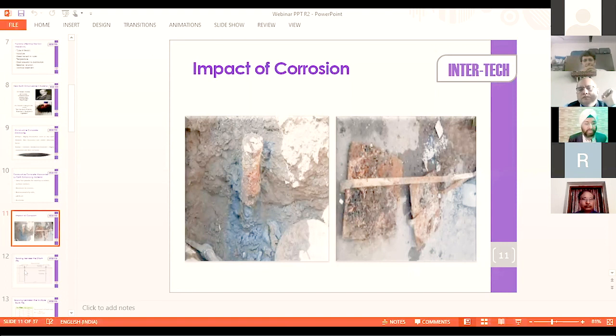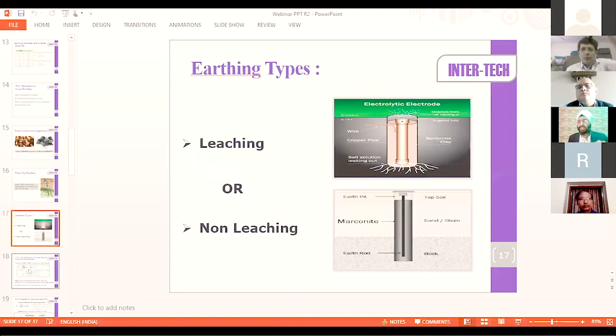Let me show you in another slide. These are two earth pits - the above one is chemical earthing, the bottom one is Marconite earthing. There are two components in any earth pit: A is the rod which carries fault current into the ground, which you see as a solid rod or bar. Second is the earth-enhancing material surrounding that electrode, which can be charcoal, salt, bentonite, chemical, or Marconite.